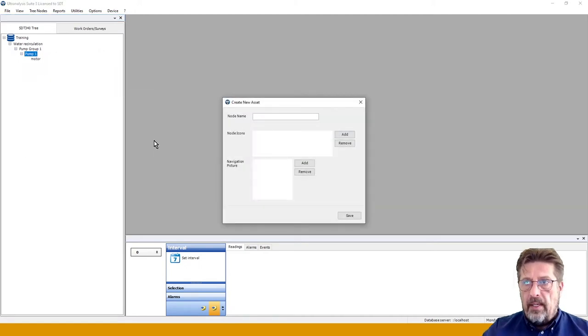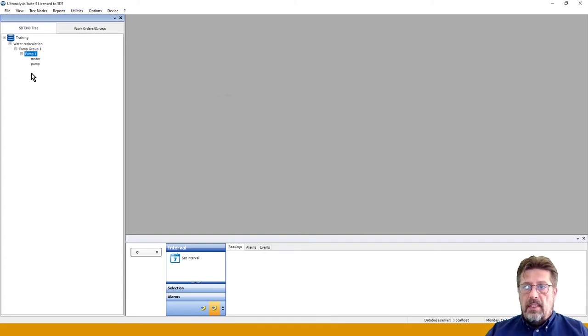So add new asset, and it's going to be pump. Note that I'm making a difference between a pump as a complete asset, so I'm using a capital P, and the pump itself, which is part of that pump asset, pump train, and I'm using a small p. It's done just because it will make it so much easier later to search the database and to understand what is what. So maybe I have a whole train, pump number one, and a backup is pump number two. But for instance, if I want just to check cavitation on a pump volute, I will search for the pump with small p. So it will make things quite easier because we have to see the difference between a pump and a pump. And it's quite important to do it in the beginning instead of repairing your database later. It will become quite painful.